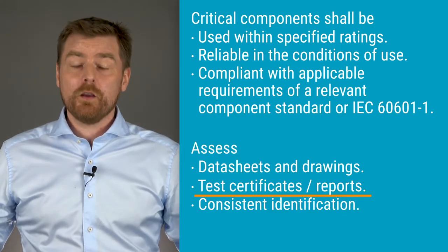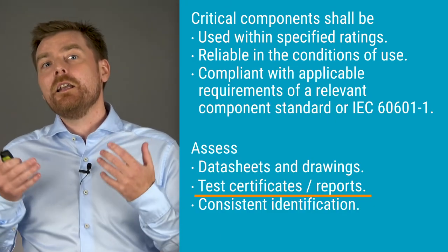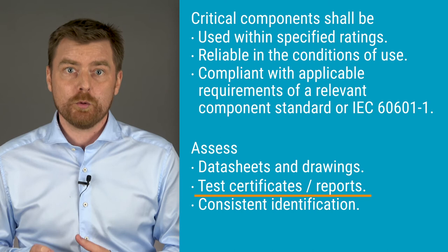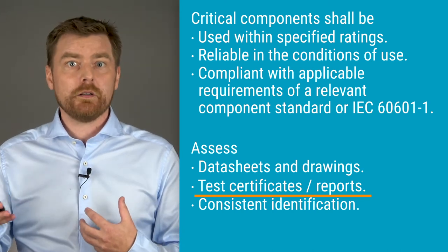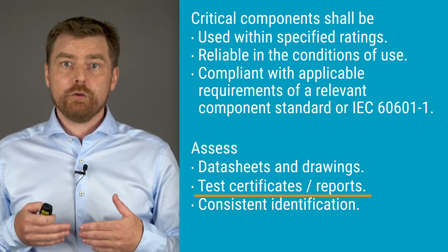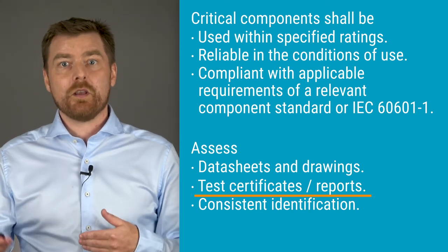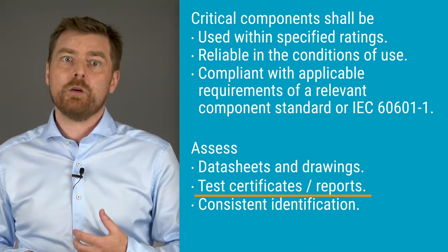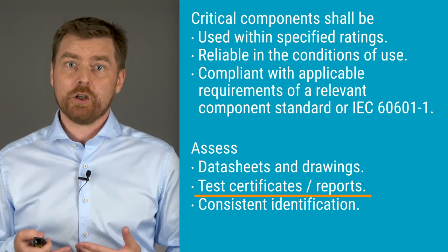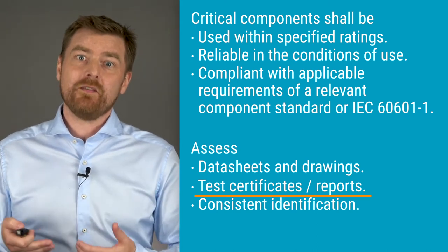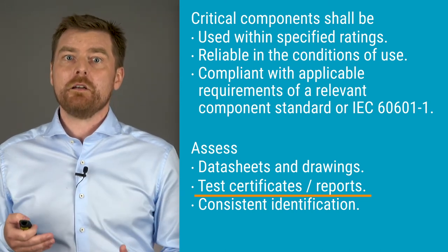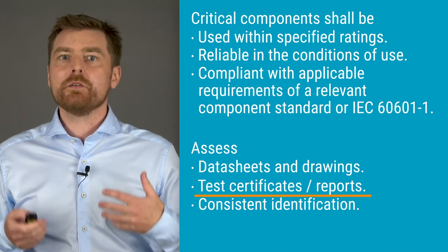This is a major pitfall, so be careful. If you can provide a valid test certificate, you do not have to retest the component to ensure that a fault cannot result in a hazardous situation. If you cannot provide a certificate, you should consider a replacement or asking the component manufacturer to perform and certify component testing. This is why you should compile and maintain this documentation during development. You can save a lot of time, effort, and money by using components that have been tested and certified by UL, TÜV-DE, or similar certification bodies.